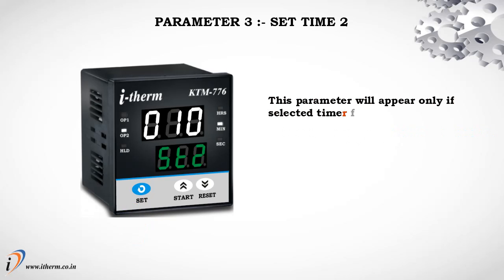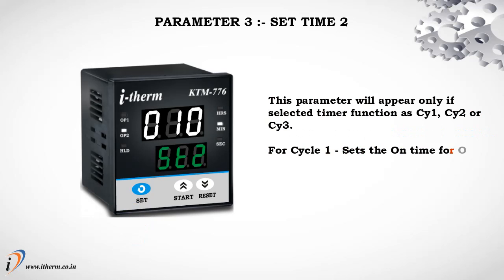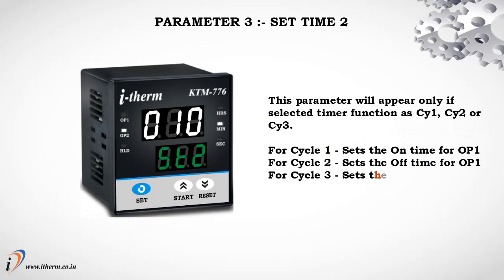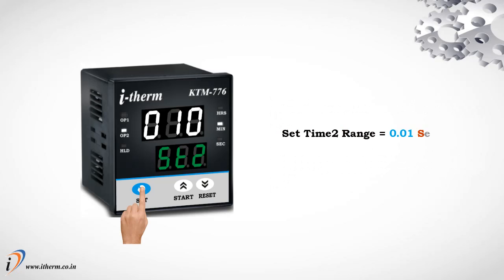Parameter 3: Set Time 2. This parameter will appear only if the selected timer function is Cycle 1, Cycle 2, or Cycle 3. For Cycle 1, it sets the On Time for Output 1. For Cycle 2, it sets the Off Time for Output 1. For Cycle 3, it sets the Reverse Time for Output 2. Set Time 2 range: 0.01 seconds to 999 hours, depending on Range 2.